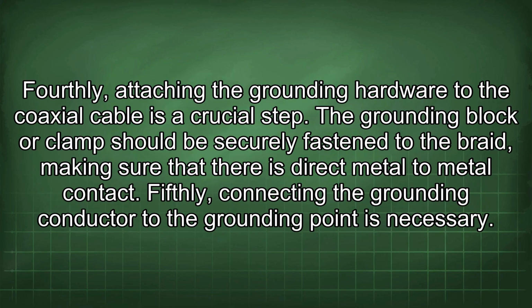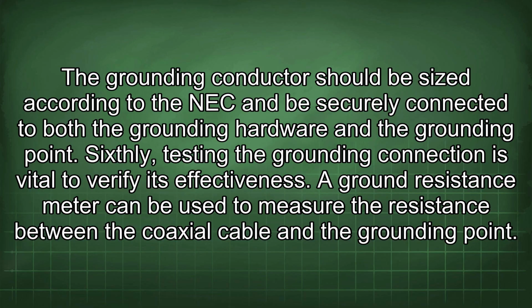Fourthly, attaching the grounding hardware to the coaxial cable is a crucial step. The grounding block or clamp should be securely fastened to the braid, making sure that there is direct metal-to-metal contact. Fifthly, connecting the grounding conductor to the grounding point is necessary. The grounding conductor should be sized according to the NEC and be securely connected to both the grounding hardware and the grounding point. Sixthly, testing the grounding connection is vital to verify its effectiveness.